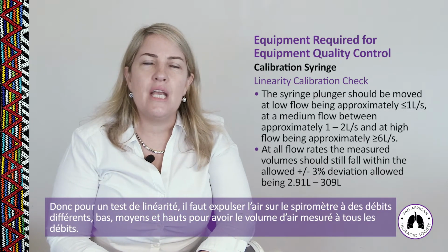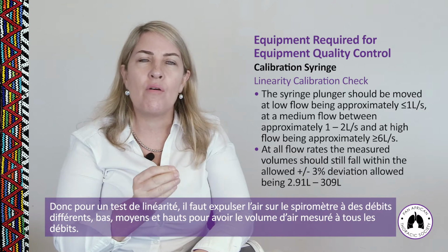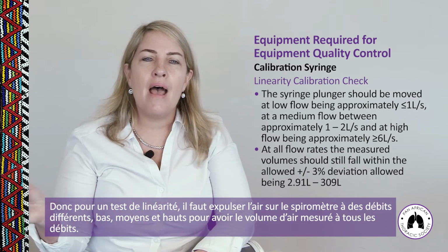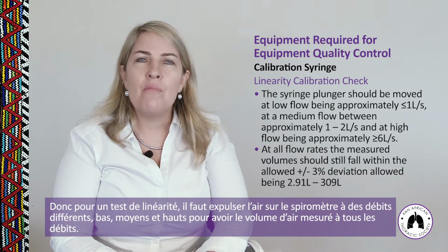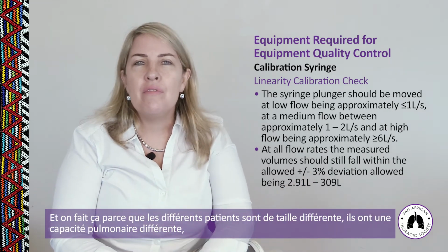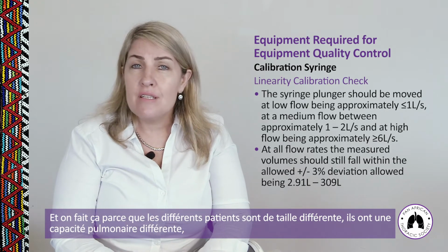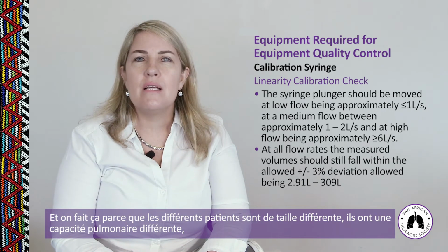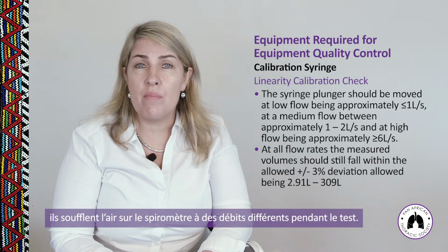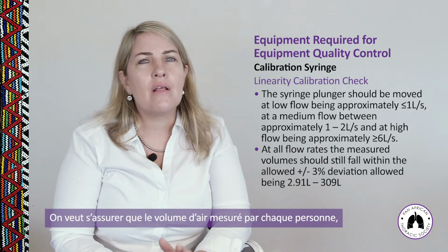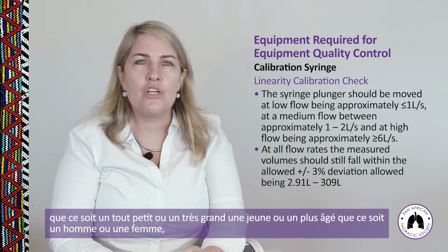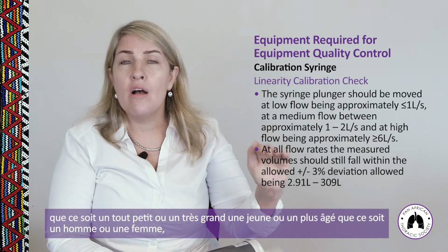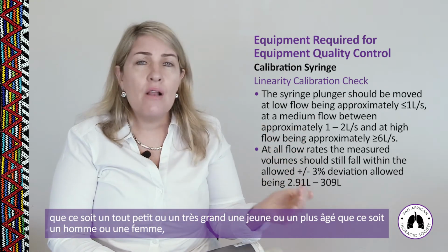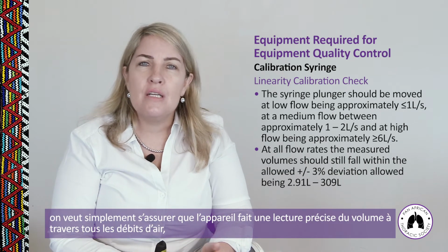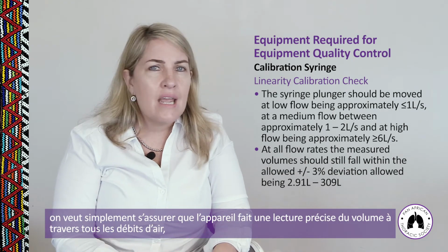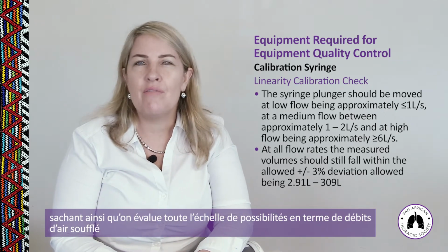So in a linearity check, you need to pump the air onto the spirometer at low, medium, and high flow rates to look at the volume of air measured at any flow. And the reason why we do this is that you have different size people with different lung volumes and different flow rates blowing onto your spirometer at different times. We want to make sure that the volume of air measured in any patient, no matter how small or tall they are, how young or old they are, whether they're male or female, we want to make sure that the machine is reading volume accurately across any flow rate so that we know that we're covering all patients when we measure volumes.